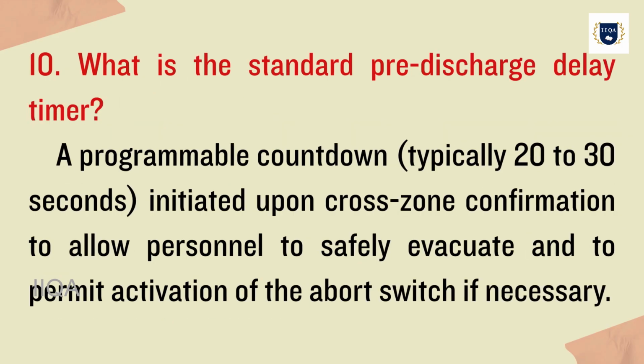10. What is the standard pre-discharge delay timer? A programmable countdown, typically 20 to 30 seconds, initiated upon cross-zone confirmation to allow personnel to safely evacuate and to permit activation of the abort switch if necessary.